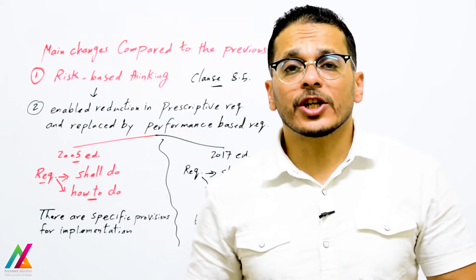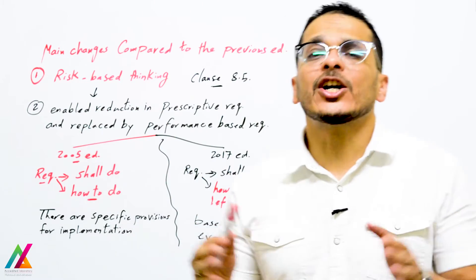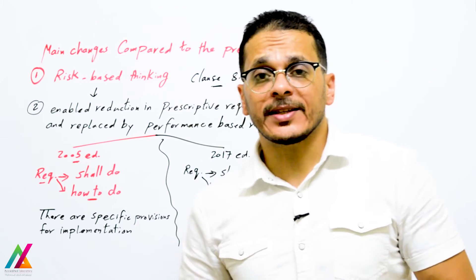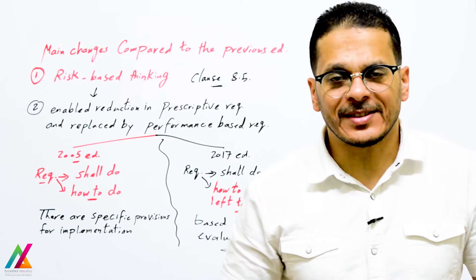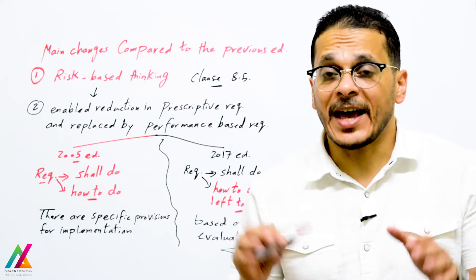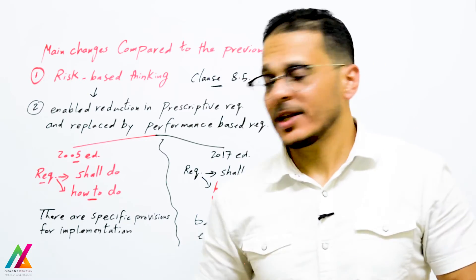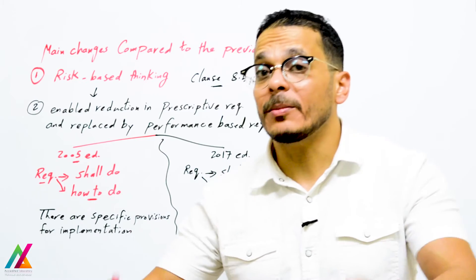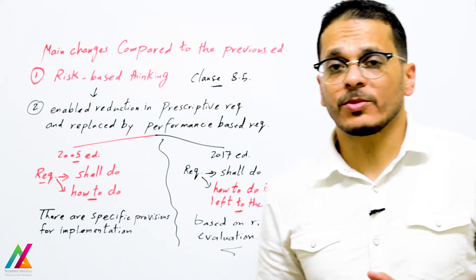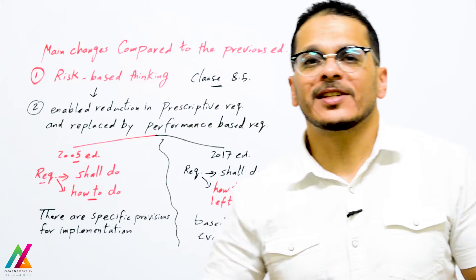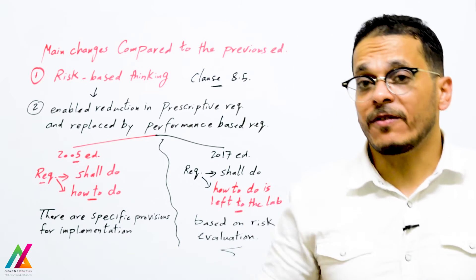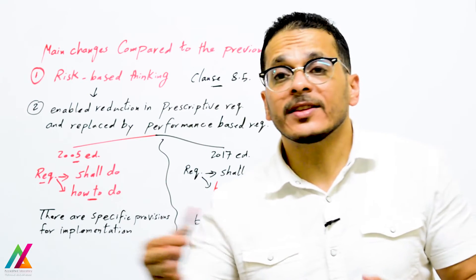By evaluating risk on each lab activity, this enables a reduction in prescriptive requirements and a reduction in the number of documents used inside the lab, replaced more by performance-based requirements. In the 2005 edition, requirements specified both what to do and how to do it with specific provisions for implementation. In the 2017 edition, the requirements specify what to do but how to do it is left to the lab, based on their risk evaluation and performance.